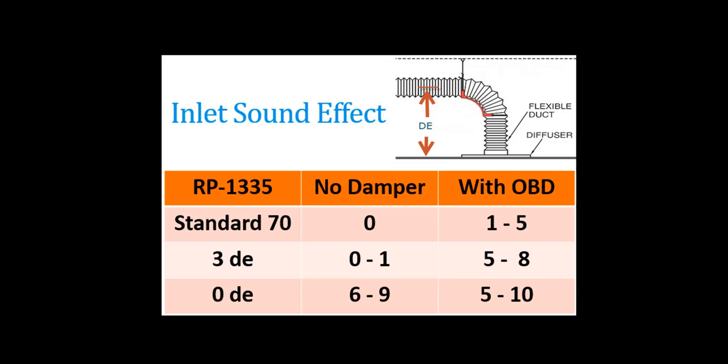The takeaways that we get from this is twofold. First is that inlet conditions do have an effect on the overall system, and thus we stress the importance of following good practices when using flex duct. Secondly, adding a damper affects the sound, and whereas we didn't discuss pressure in this podcast, the pressure also sees similar effects.